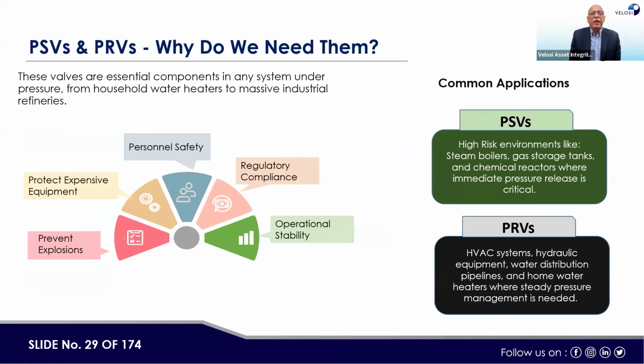This is the purpose. Basically, why are they installed? Number one, to prevent explosions and protect expensive equipment, which should not burst due to high pressure. Personal safety, because if equipment bursts, it may cause an explosion. Regulatory compliance and operational stability. PSVs and PRVs protect high-risk environments like steam boilers, gas storage tanks, vessels, and chemical reactors, where immediate pressure release is critical. Whereas PRVs are applied for liquid systems, HVAC systems, water distribution pipelines, and home water heaters.